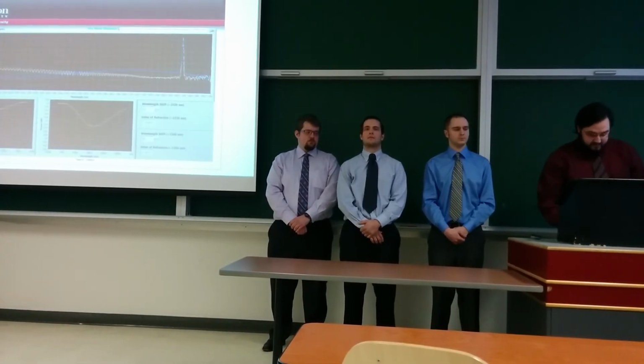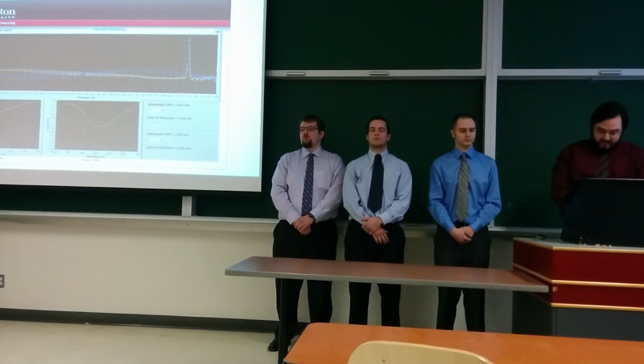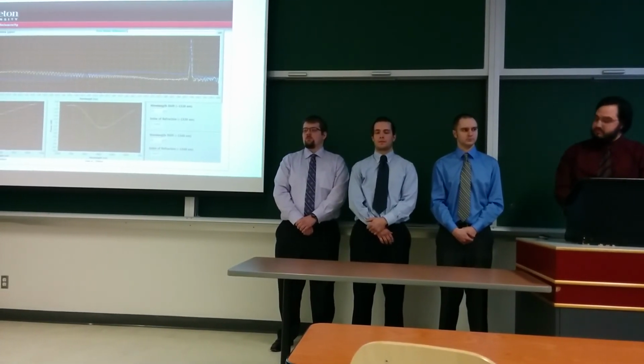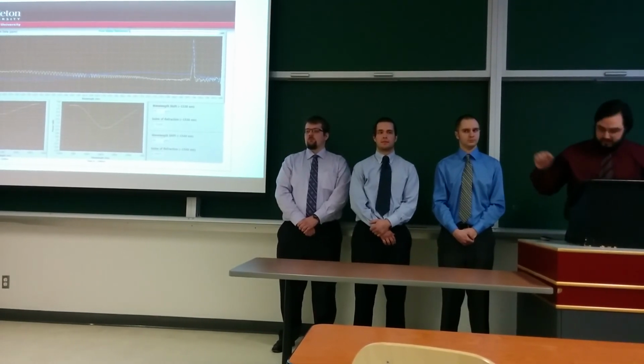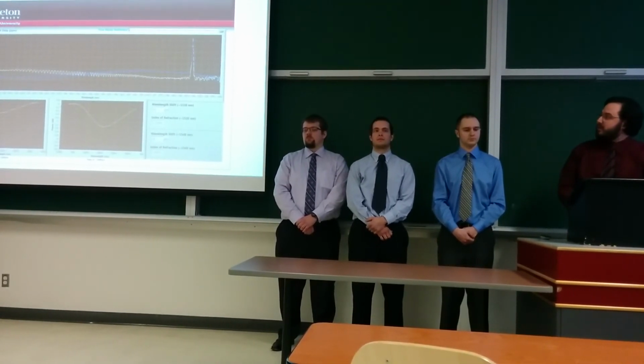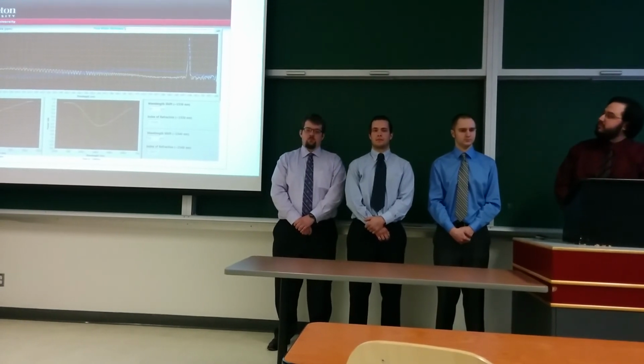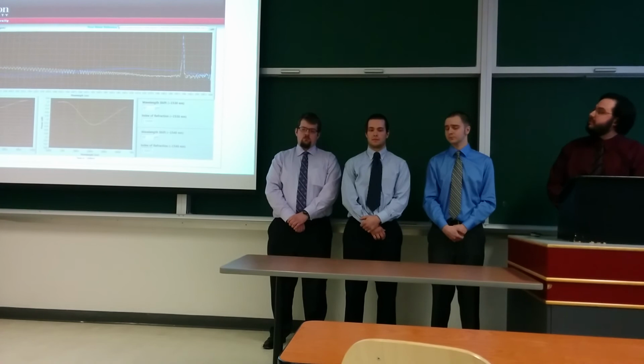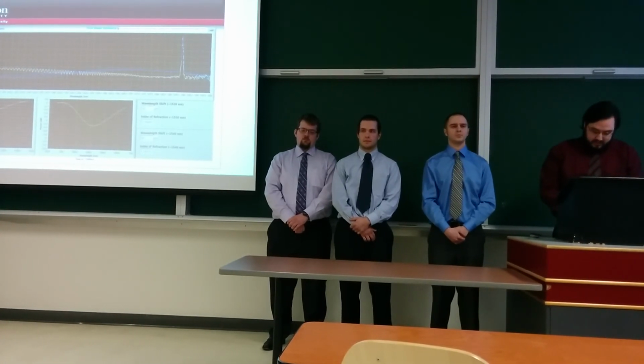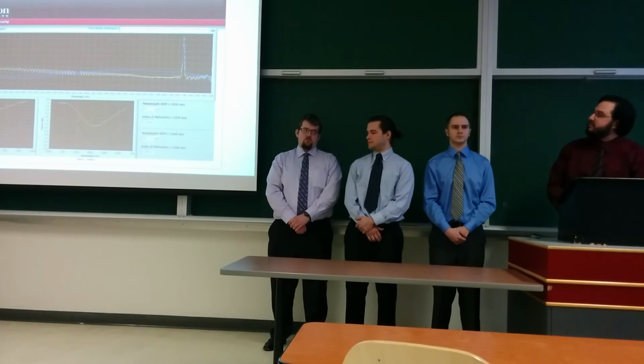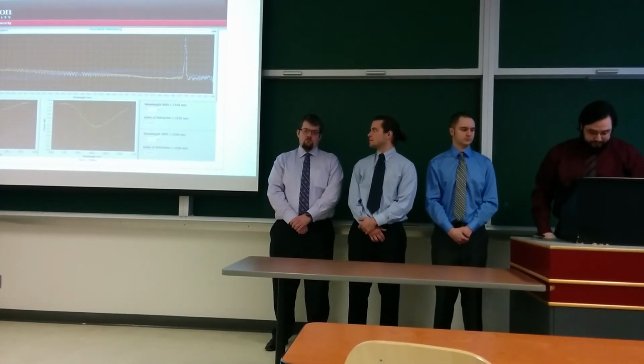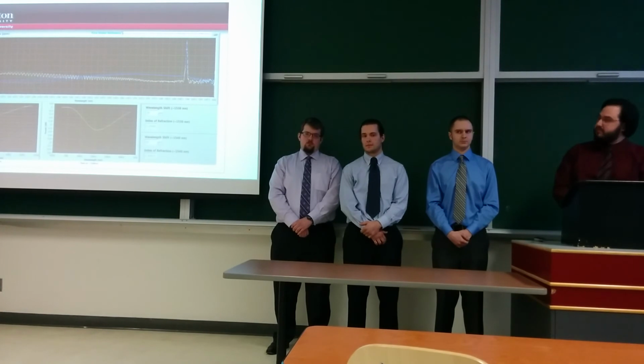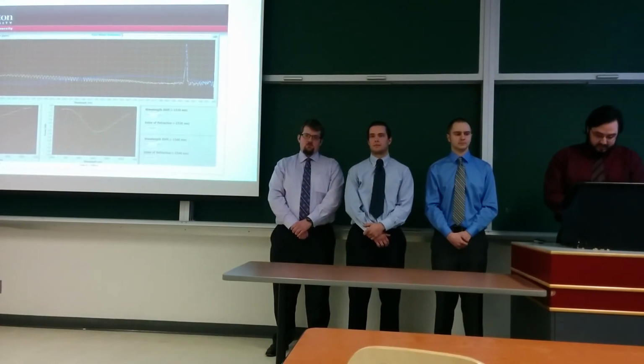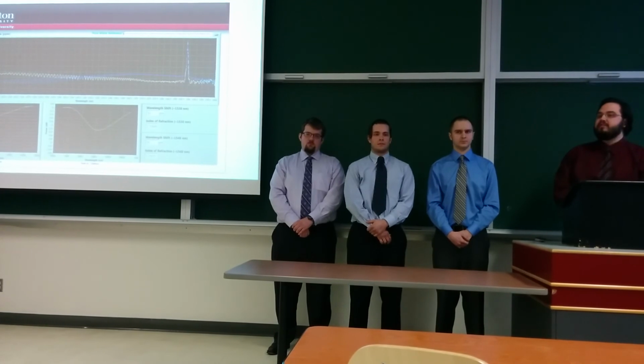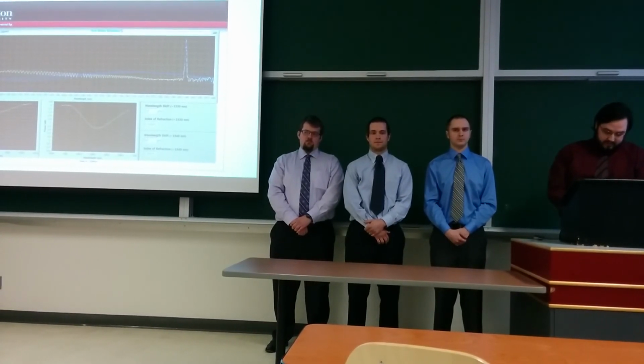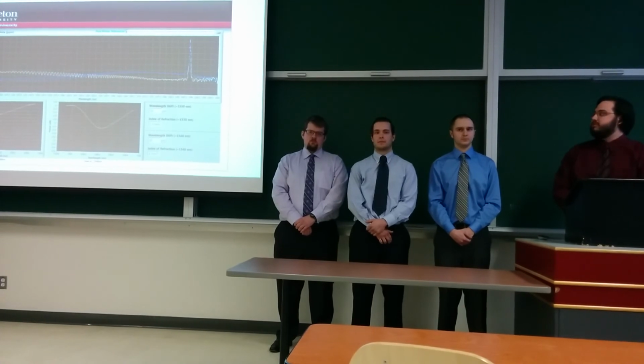We've also developed a more complex interface to show more detail about the interaction between the pure water reference and the spectrum of water being monitored. The main window here shows the full pure water spectrum in blue and the water being monitored in white. The 2 windows on the left show close-ups of the peaks around 1530 nanometers and 1540 nanometers. And the window on the right shows the wavelength shift and index of refraction for those same peaks. This interface was developed for someone who has more knowledge of the inner workings of the actual system and wants to check the actual wavelength shift and its corresponding index of refraction in order to do more in-depth analysis or to troubleshoot the system.